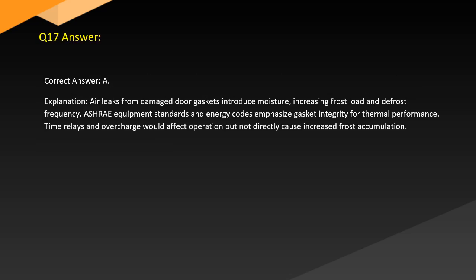Answer. Correct answer: A. Explanation. Air leaks from damaged door gaskets introduce moisture, increasing frost load and defrost frequency. ASHRAE equipment standards and energy codes emphasize gasket integrity for thermal performance. Time relays and overcharge would affect operation but not directly cause increased frost accumulation.